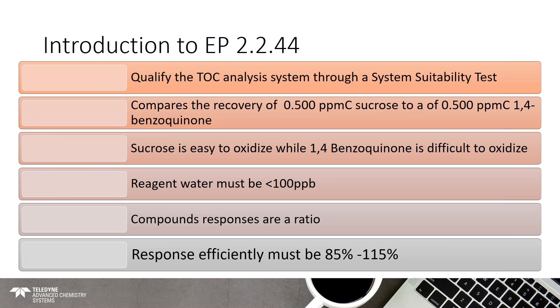Here's the introduction to EP 2.2.44. If you look at the method, it's only about a page, so I strongly encourage you to read it. Basically, it qualifies the TOC analysis system through a system suitability test. Any TOC technique can be utilized — by technique I mean oxidation-type technique. So you can use a membrane conductivity system, a combustion system, or a UV persulfate system like we used for this study. You compare the recovery of 0.5 ppm of carbon from sucrose to 0.5 ppm of carbon from 1,4-benzoquinone.